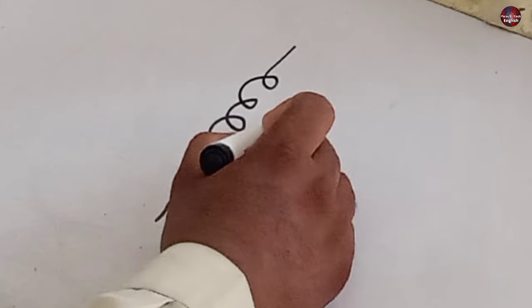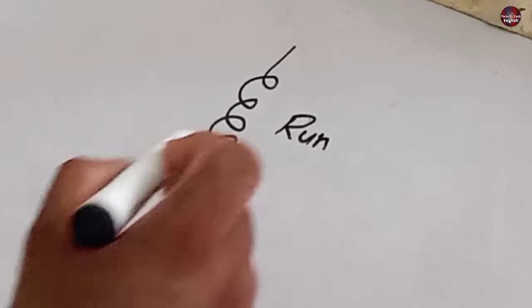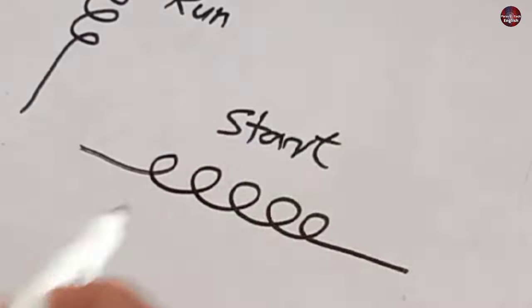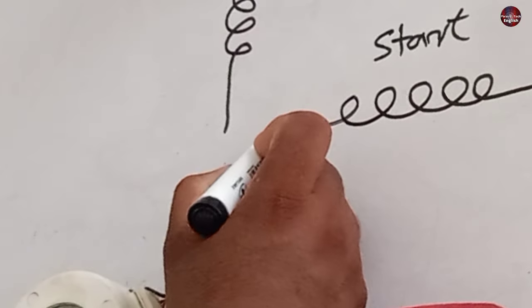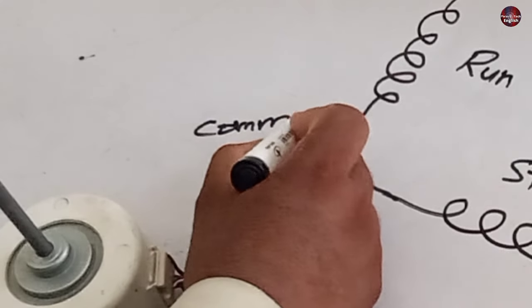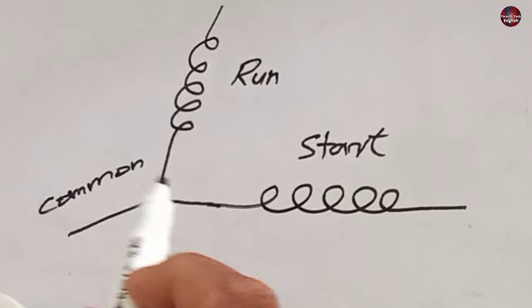This is the first winding, which I will name as run winding. Then this motor has a second winding, which I have named as start winding. One end of these windings is connected with each other. This end will be named the common point. This is how the motor is connected internally.